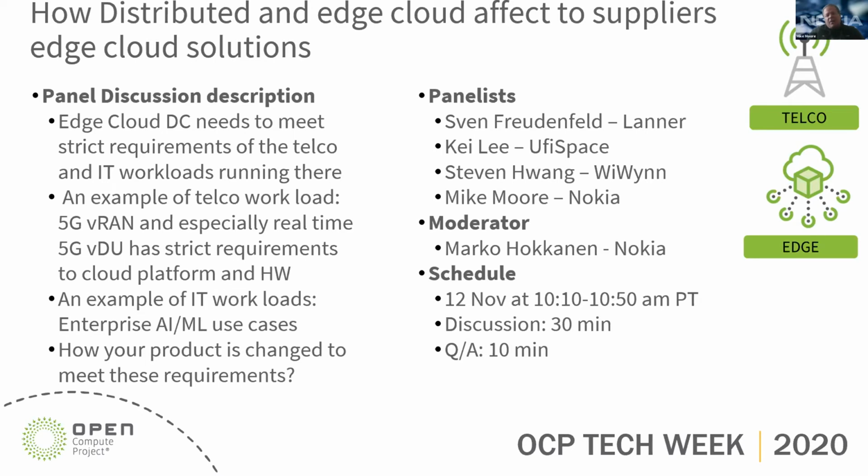So we not only went and looked at the NEBS certification documents, GR63 core and 1089 core. We also went out and surveyed all of our customers, especially our tier 1 customers in North America, and got their edge telco equipment documentation. And we put all those together and really created a superset of requirements. And we use that superset of requirements to really drive the open edge design. And so there's the environmental concerns at the edge that we definitely needed to address.